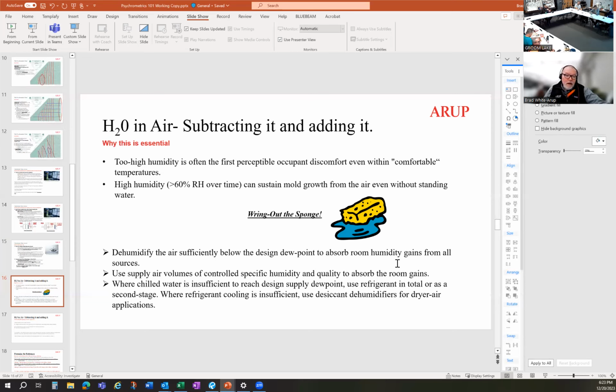It's good discussion. And one thing I found about blow through coils, and I've used both: up here in the Northeast, we use draw through almost exclusively. In package equipment, you get blow through sometimes by default. That's just how they make them. But I've used draw through on 99% of the projects I've ever done. The only ones I've used blow through were in the Southwest or in Colorado, where it's relatively dry and dehumidification is not much of a concern. They want to add that heat to the coil, and they don't need to get it down that cold because they're not removing as much moisture.